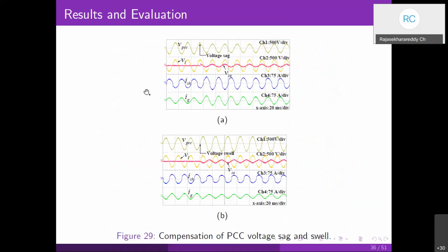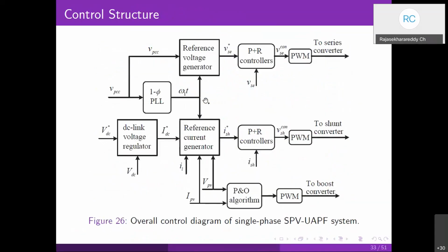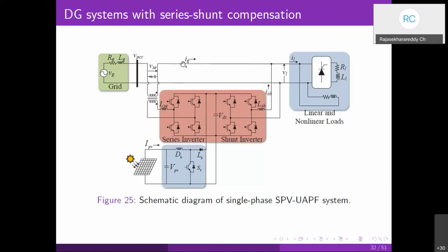Okay, here is the case when we have a voltage sag. When there is a voltage sag, the series converter comes into the picture. The series converter injects voltage in phase with your PCC voltage in order to maintain the load voltage constant. So you can see this orange waveform, which is constant irrespective of your grid voltage variation. When it is injecting voltage in series with the grid, the line current is coming out of the positive terminal, so it is supplying active power. That active power is being taken from the PV generation, so a part of the PV generated active power is supplied through the series converter. That means the shunt converter will be relieved from part of the PV generation.